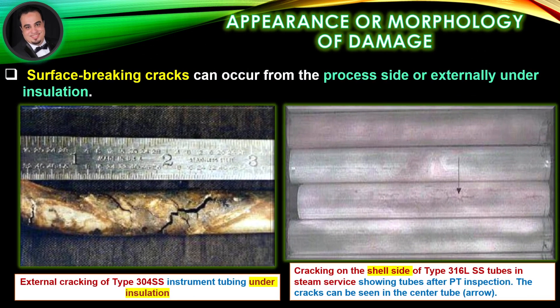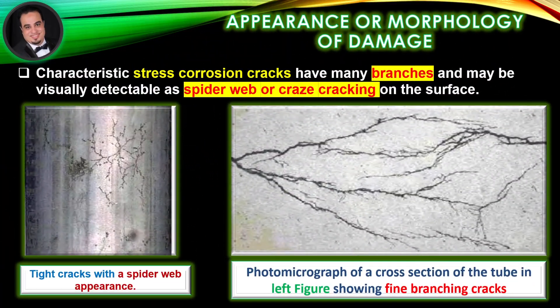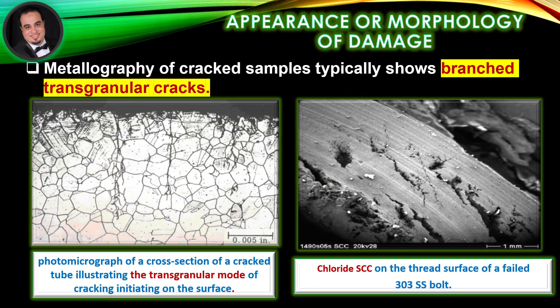Appearance or morphology of damage, as illustrated in figures: Surface breaking cracks can occur from the process side or externally under insulation. Characteristic stress corrosion cracks have many branches and may be visually detectable as cracking on the surface. Metallography of crack samples typically shows branched transgranular cracks.